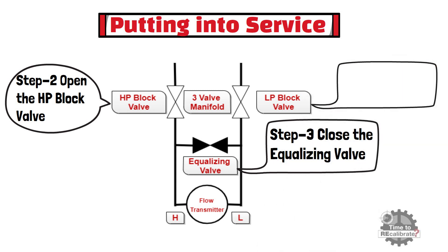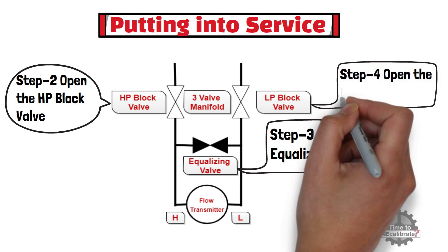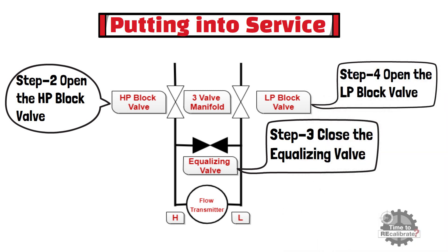In fourth and final step, open the LP block valve by rotating valve in counterclockwise direction. The transmitter will now be able to indicate the correct differential pressure between the high and low pressure taps, and transmitter is now considered to be in service.